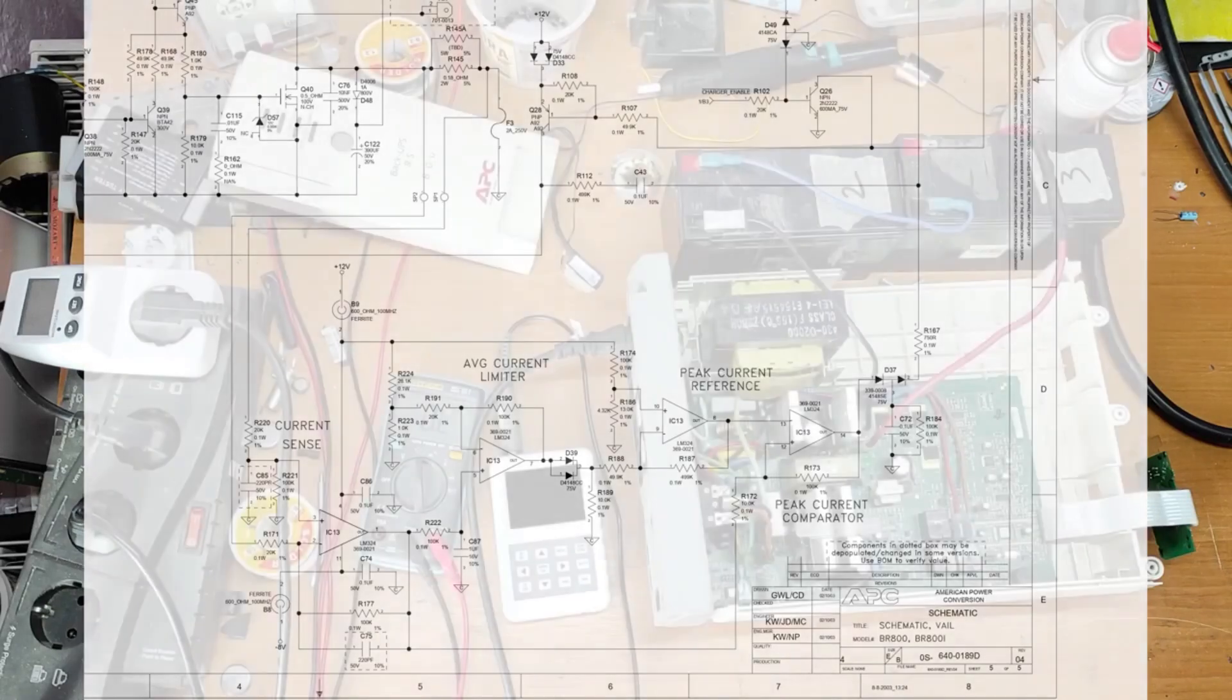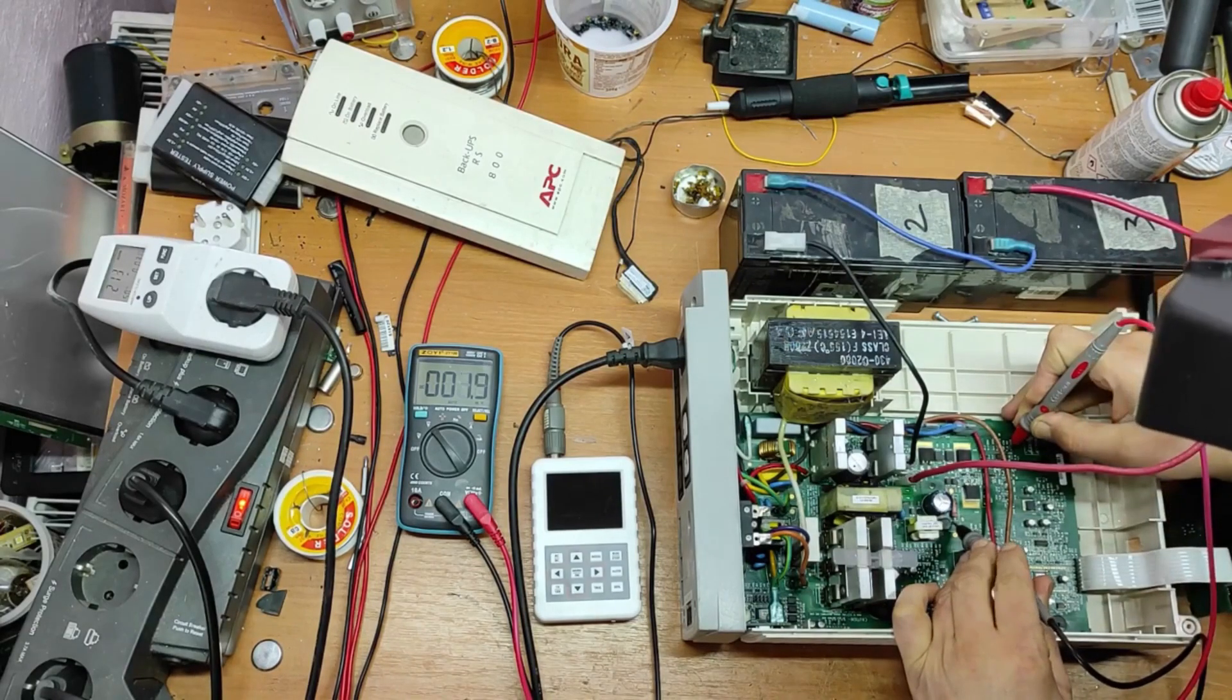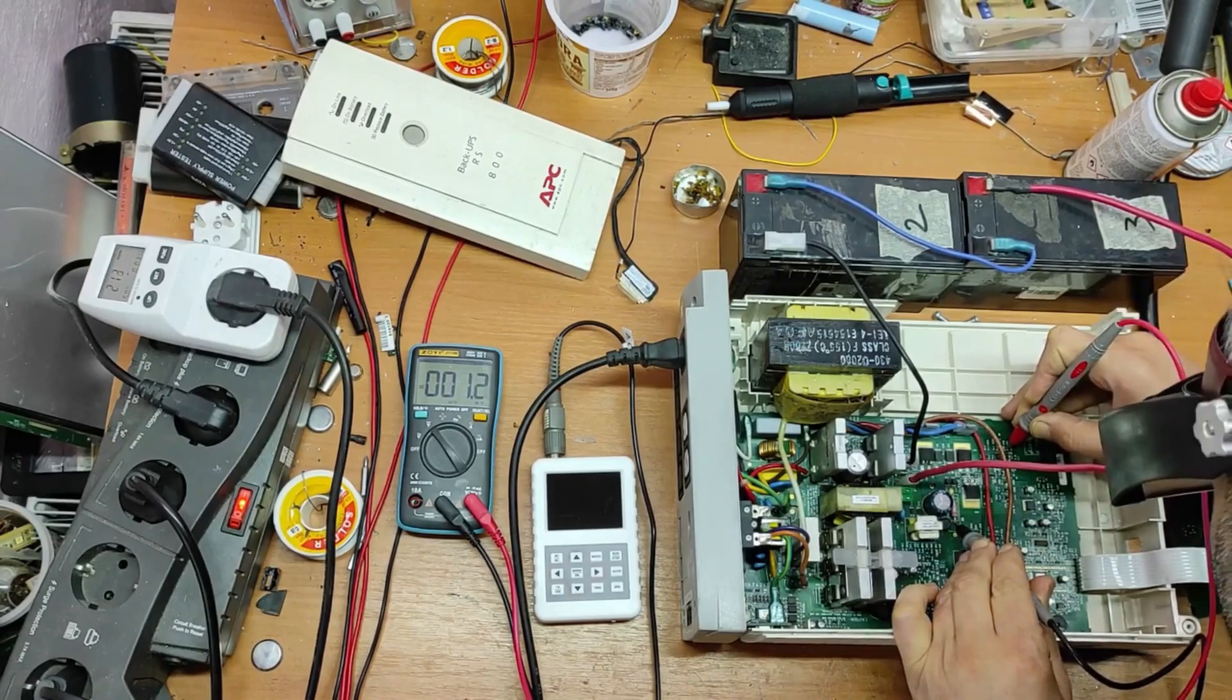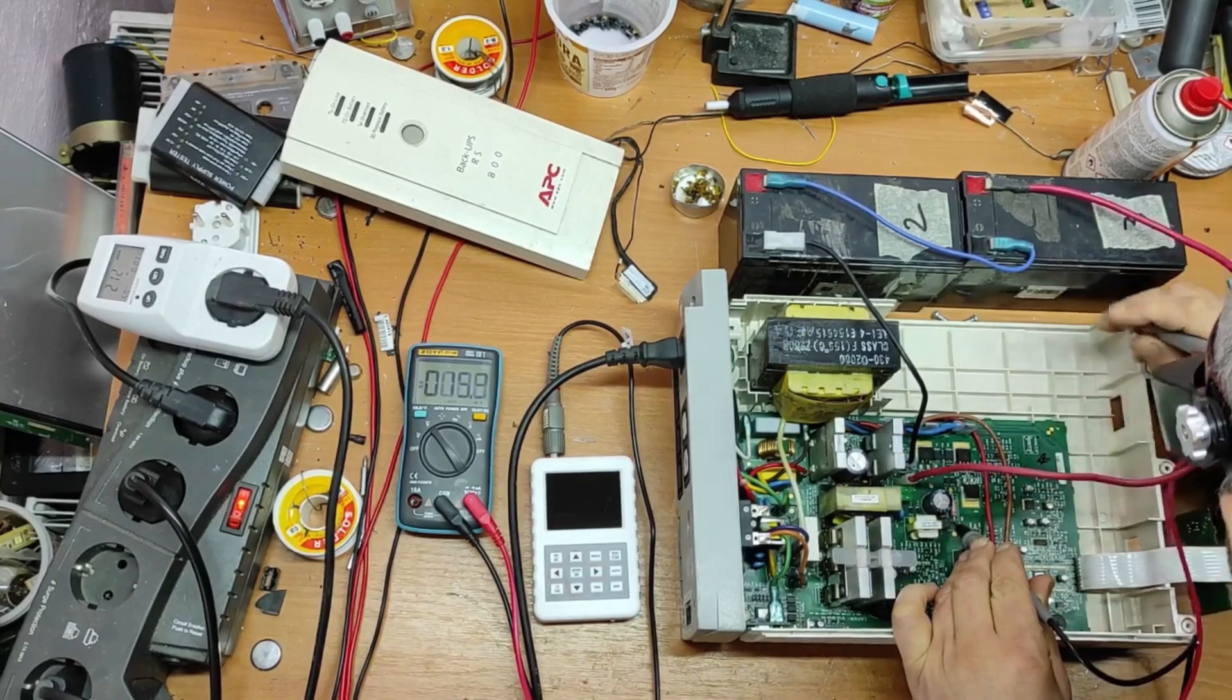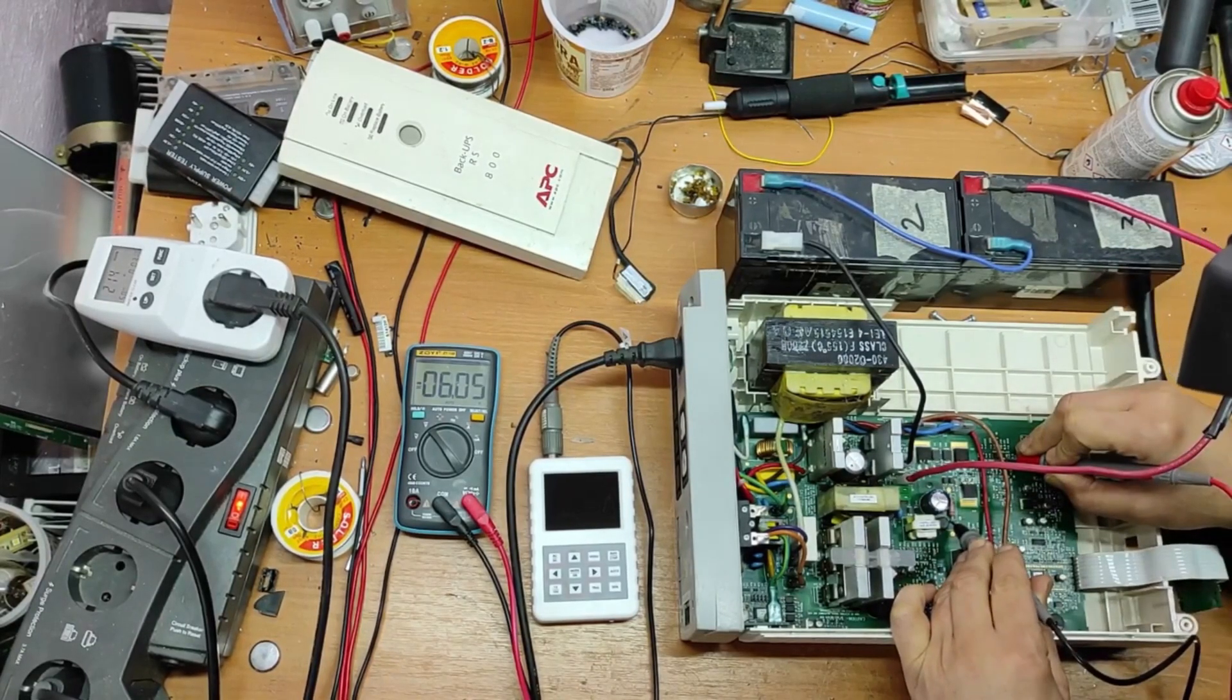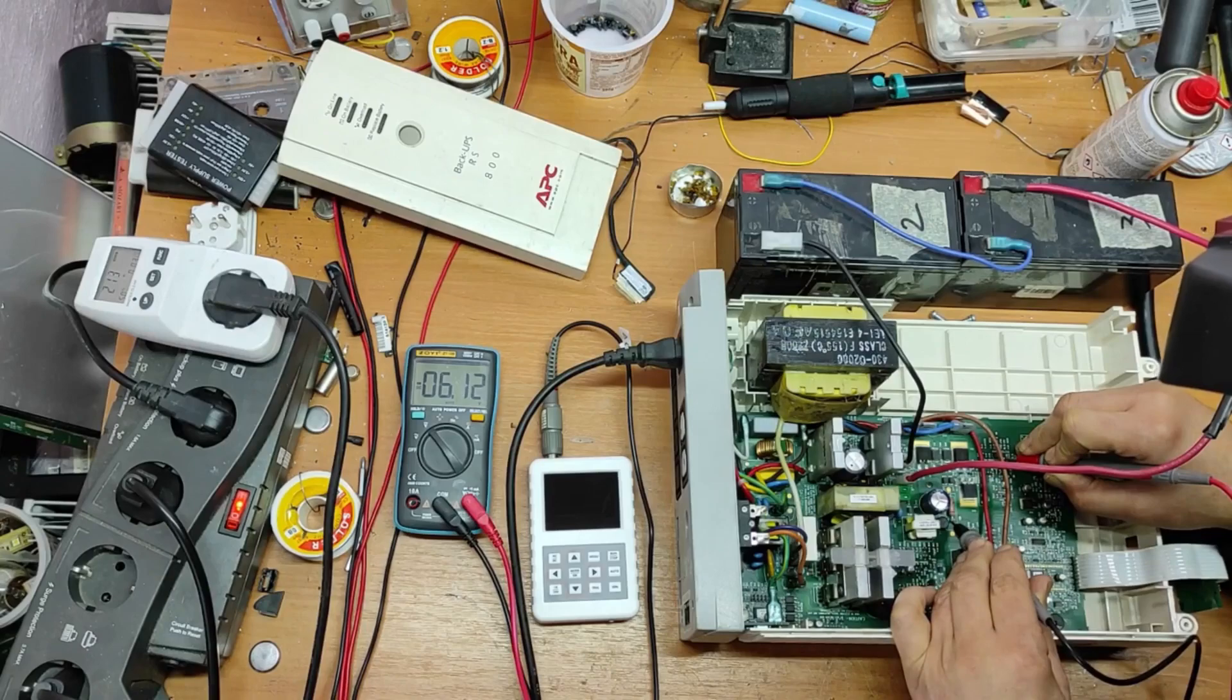Now, let's measure the supply voltage for IC 13. Pin 2 and 3 are the input from shunt resistor. It's good. Pin 4, it's 12 volts. It's good. Pin 11, it's not good. This should be minus 8 volts. It's only minus 6 volts. And that's the problem.